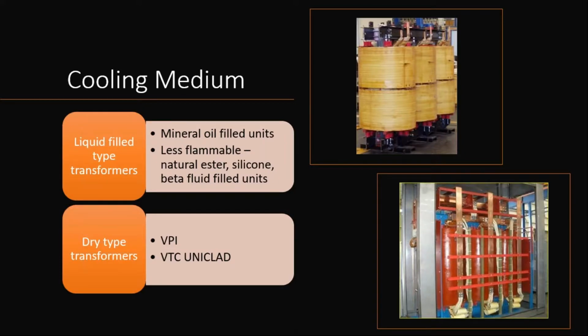All of these transformer applications which we discussed in the previous slide can be made in either liquid or dry types, depending on the rating of the transformer, size in kVA, voltage class, and the user's site limitations. They will decide which type of transformer they want. Liquid is most common, and there's pretty much no limit to the size or voltage class. Under liquid, there is regular mineral oil or less flammable liquids, which are natural esters. Depending on the location of these transformers, the customer will have their own site code to follow, and they may go for a less flammable liquid; otherwise mineral oil is most commonly used.